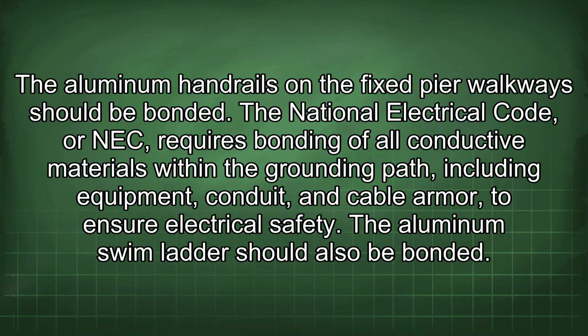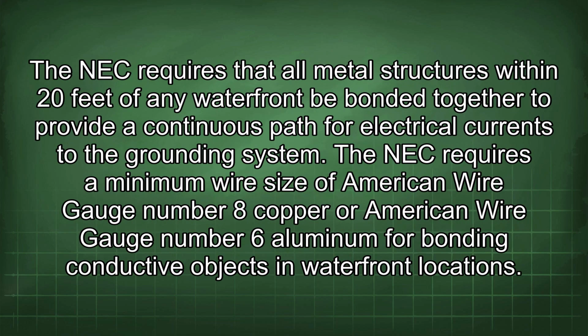The aluminum handrails on the fixed pier walkways should be bonded. The National Electrical Code, or NEC, requires bonding of all conductive materials within the grounding path, including equipment, conduit, and cable armor to ensure electrical safety. The aluminum swim ladder should also be bonded. The NEC requires that all metal structures within 20 feet of any waterfront be bonded together to provide a continuous path for electrical currents to the grounding system.